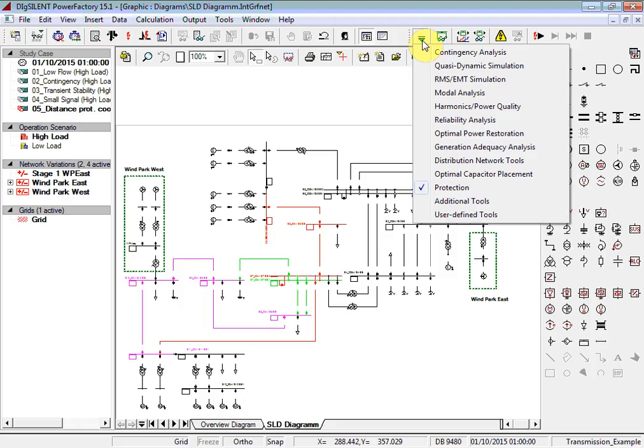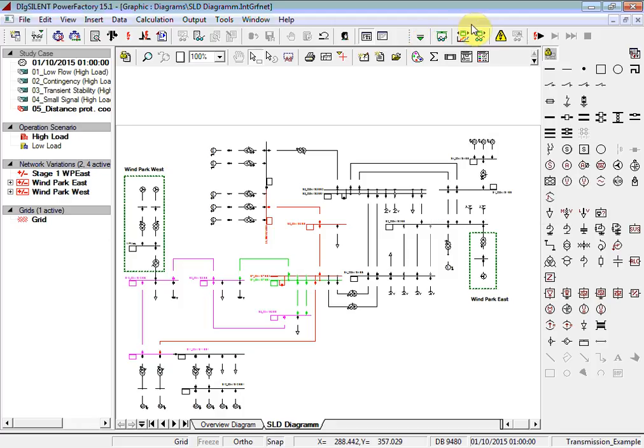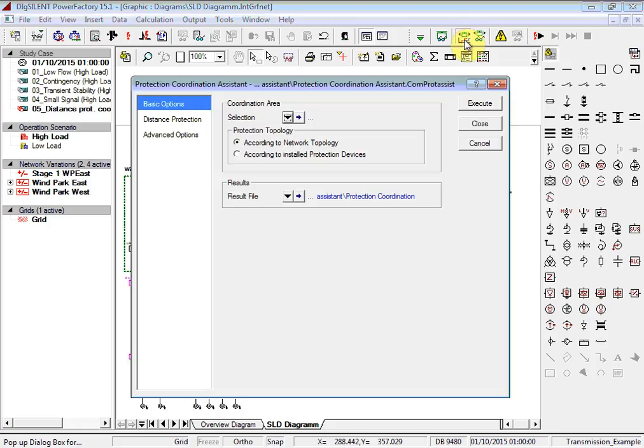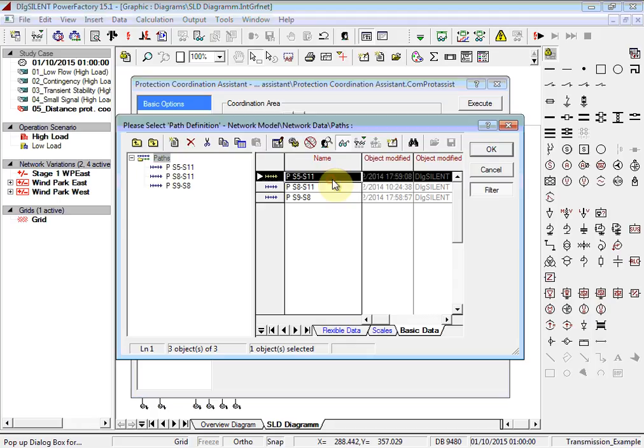Make sure that the toolbox is selected to the Protection toolbox. Then choose the Protection Coordination Assistant icon. First, we must tell the Coordination Assistant which part of the network we wish to coordinate. This can be done by selecting the paths that you wish to coordinate. Choose the option here, Select Paths. These are the 3 paths we already have defined. Multi-select those paths and select OK.